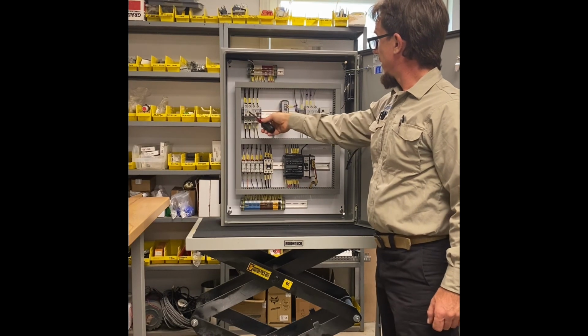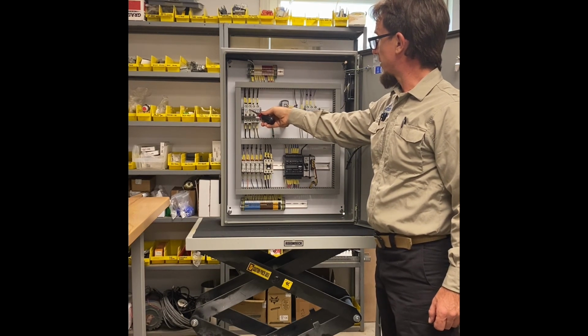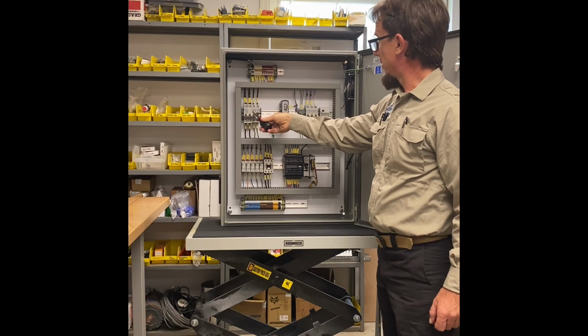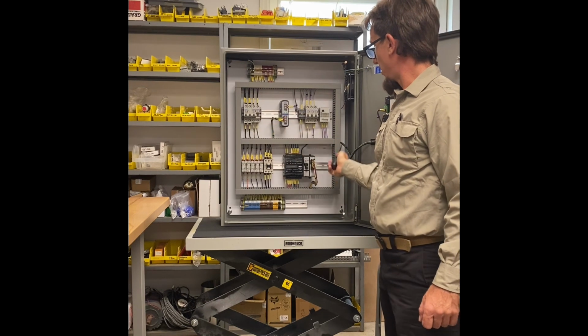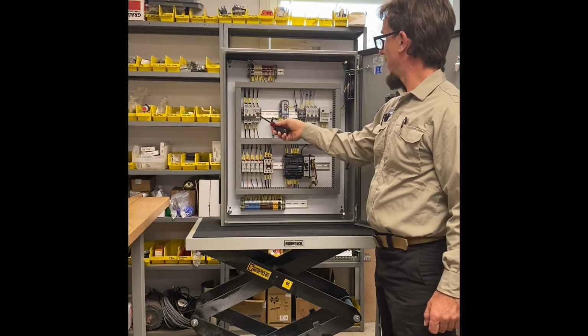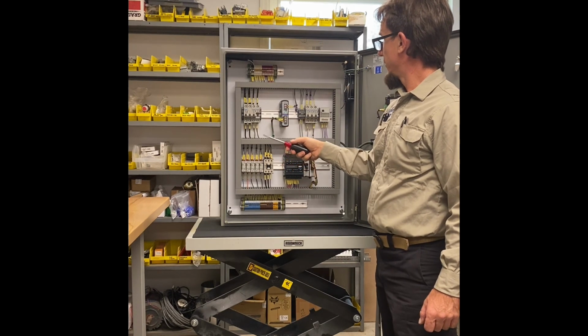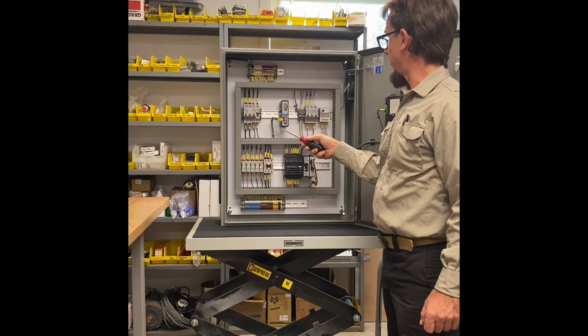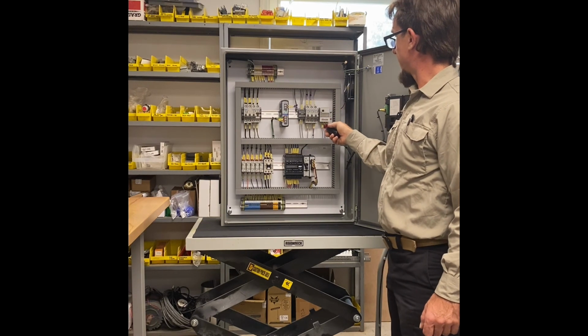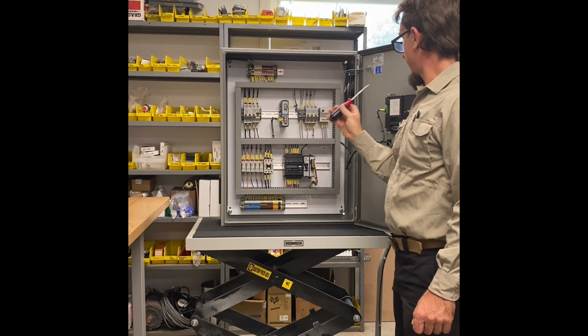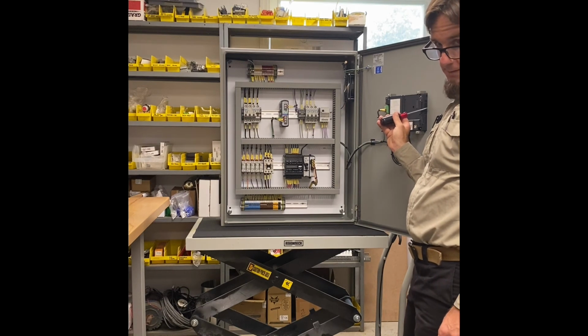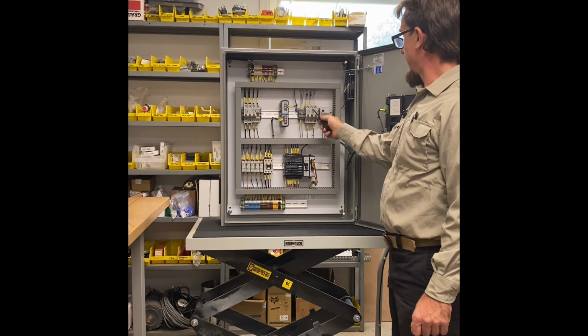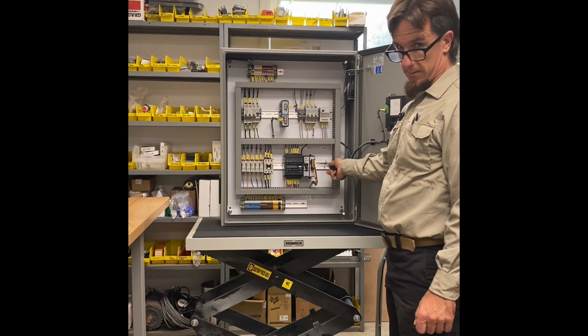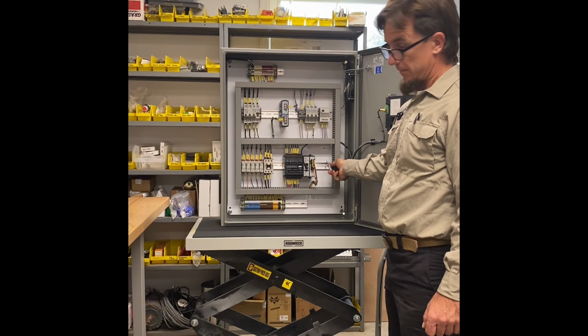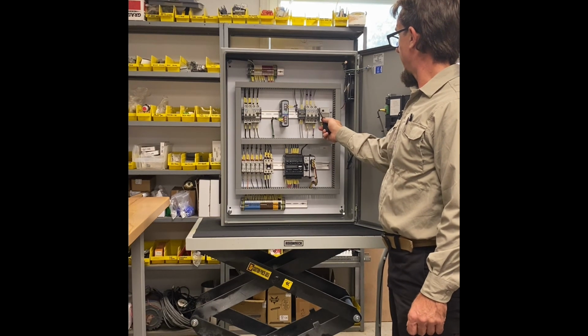I have our Panduit. This is our booster pump control circuit breaker. This is our control circuit breaker, rather. And that control runs all of the 120 volts in the panel. And then we have our 24 volt DC circuit breaker, which powers up our DC power supply, which then powers up these three circuit breakers. One circuit breaker feeds my operator interface, otherwise known as the HMI. One of them is for future for a cellular modem or Ethernet, and the last one is for the fan.